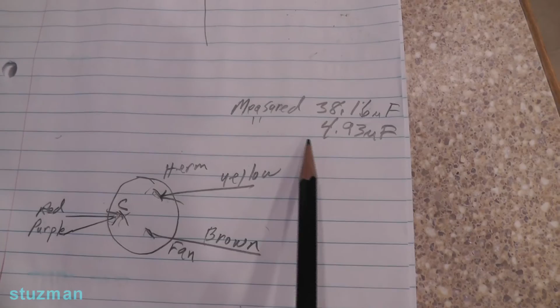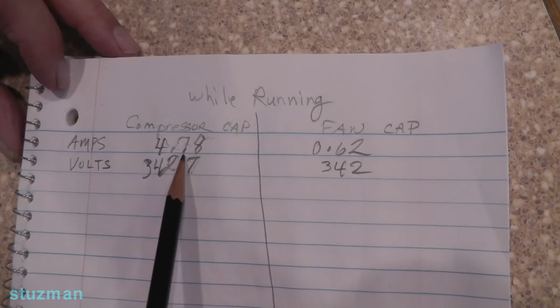All right, to start off, let's write down the measurements we made with the power off. We were using a capacitance meter. For the compressor cap, we had 38.16 microfarads, and for the condenser fan cap, we had 4.93 microfarads. Now we came back and took the measurements while it was running. We measured the amps for the compressor cap, that's for the Herm wire, and we got 4.78. The volts on that capacitor was 342.7, and on the fan capacitor, we had 0.62 amps and 342 volts.